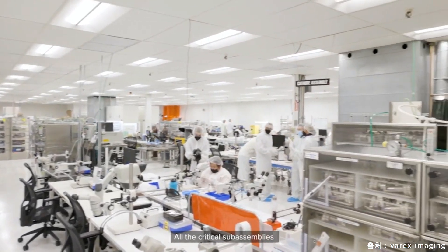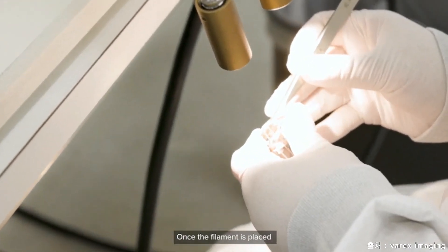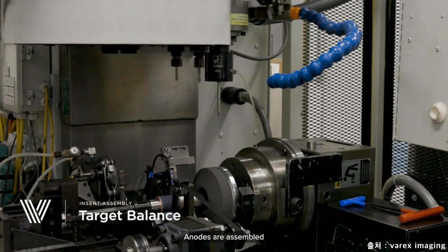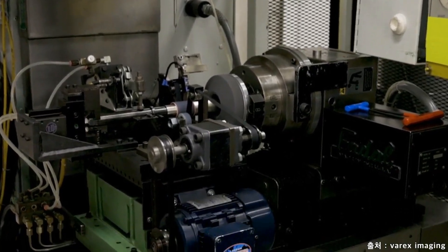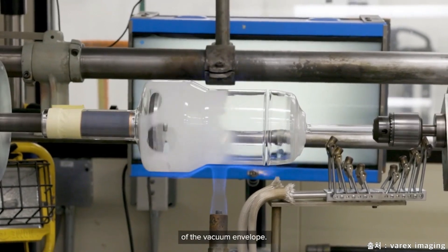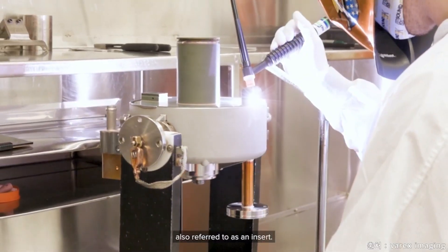Once the components have completed in the manufacturing services area, they enter the clean room to be assembled into the vacuum envelope in the insert assembly area. All the critical sub-assemblies come together in insert assembly. The cathode assembly team sets a filament in a cathode head to achieve proper imaging conditions. Once the filament is placed in the cathode assembly, the future imaging capabilities and image quality in the medical application of the x-ray tube are set. Anodes are assembled and precision balanced to support rotational speeds between 3,000 RPM and 11,000 RPM, assuring rotational stability during x-ray tube imaging. The final step in insert assembly is the hermetic sealing of the vacuum envelope. The cathode, anode, and vacuum envelope are joined through welding or fusing glass to create the x-ray tube assembly, also referred to as an insert.